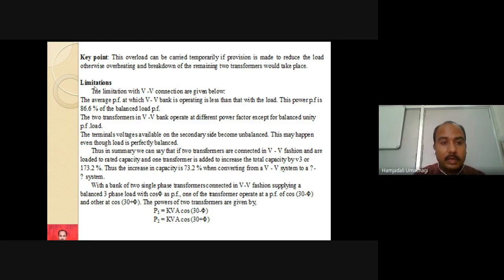That is the meaning. Now, what are the disadvantages or limitations of VV connection? The first one is that the average power factor at which the VV bank operates is less than that of the load. This power factor is 86.6% of the balanced load power factor. The two transformers in the VV bank operate at different power factors, except for a balanced UPF load. Both will operate at the same power factor only if I connect a balanced resistive load, that is UPF. If it is leading or lagging, then both transformers will operate at different power factors.